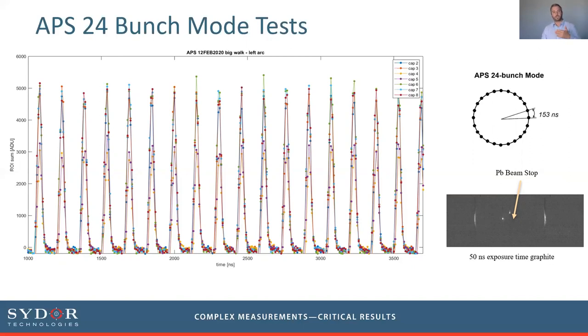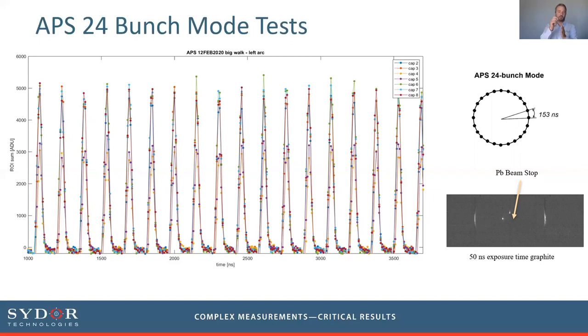By drawing a region of interest around the intensity in the diffraction ring, we can pull out a single data point — a single intensity value — as shown in the plot on the left. We set the device up to change the timing delays of each capacitor relative to the synchrotron bunches, such that the frame exposures were marching through the timing of the synchrotron bunch arrival. This shows how we can lock into the timing of a single x-ray bunch and synchronize exactly, enabling really amazing temporally resolved experiments locked to the timing of the ring.